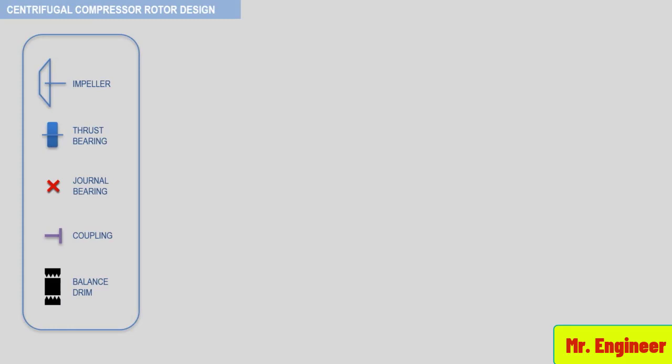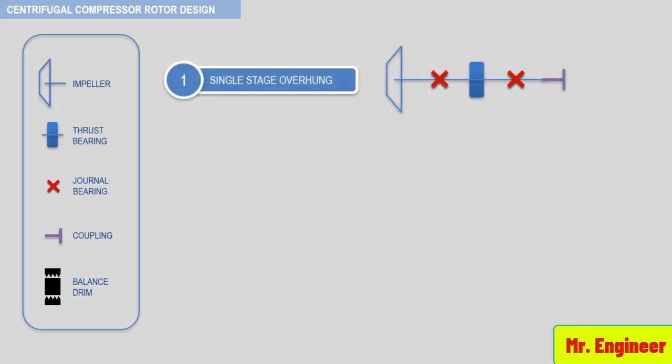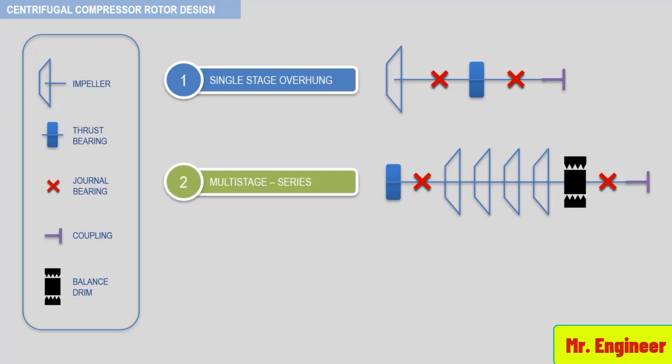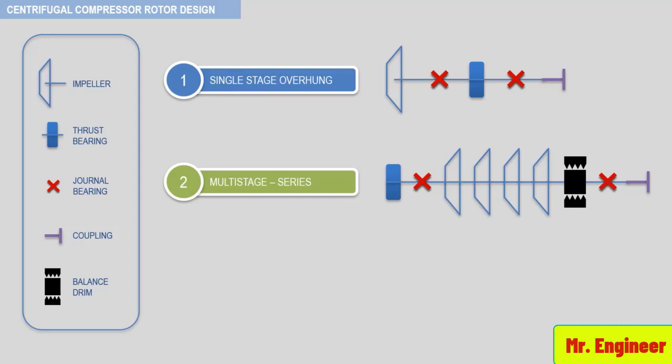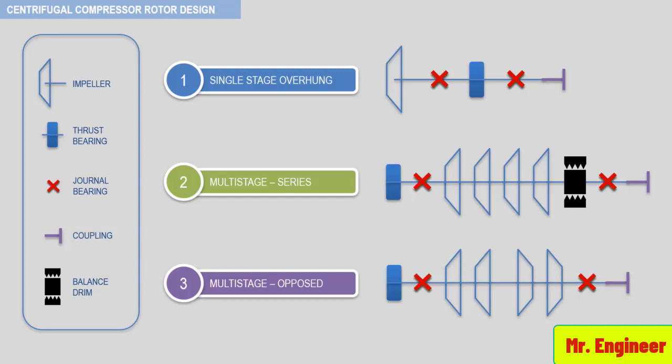There are three basic rotor configurations, and these are single-stage overhung, multi-stage series, and multi-stage opposed arrangements, as depicted here. Usually, single-stage overhung and multi-stage opposed arrangements do not incorporate a balance drum, since the rotor thrust values are low enough to be accommodated by a thrust bearing.